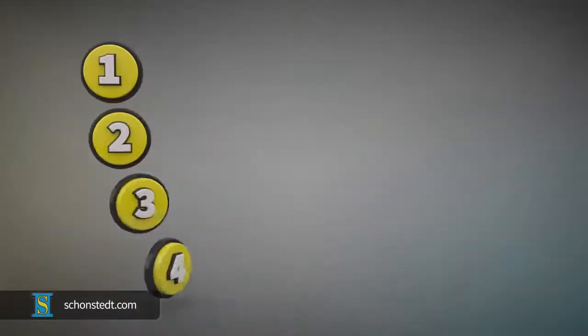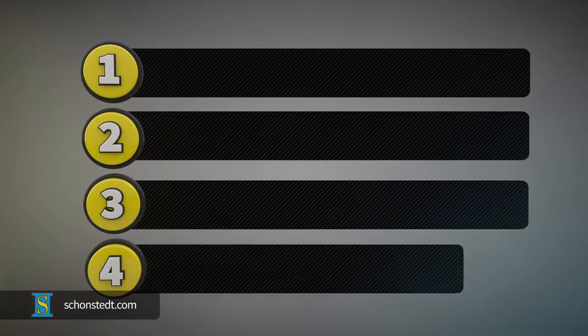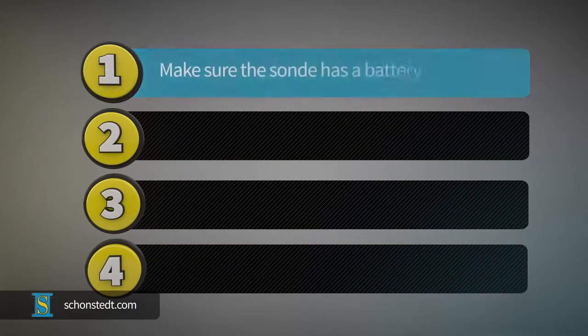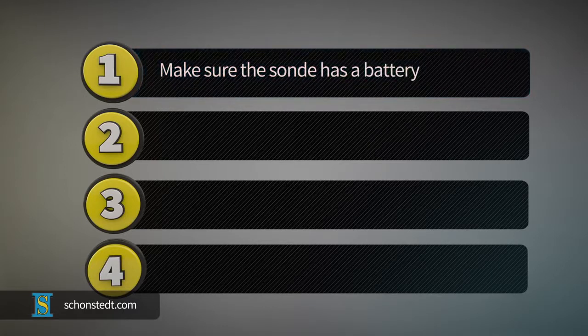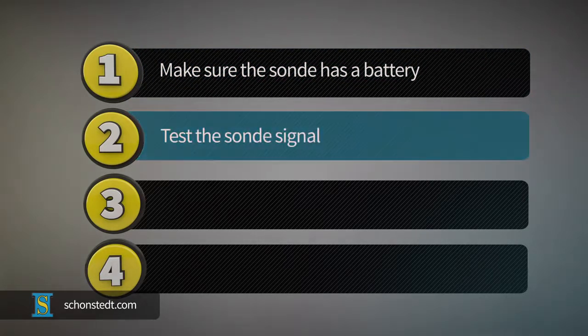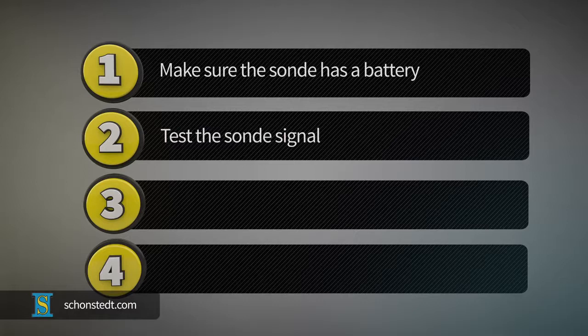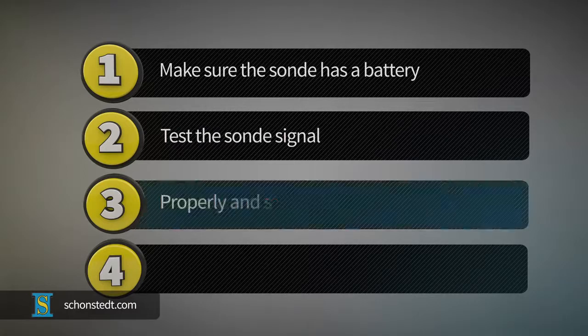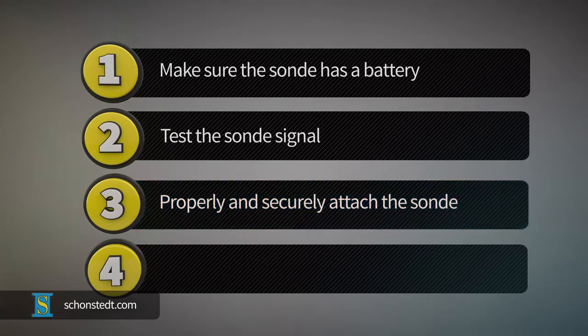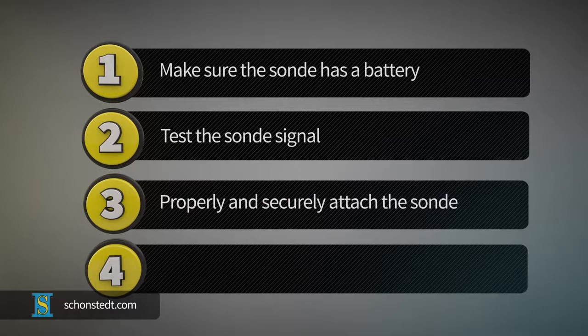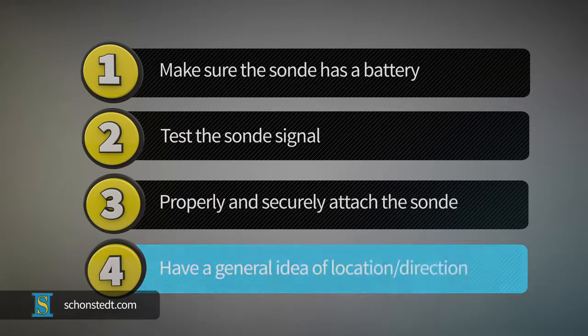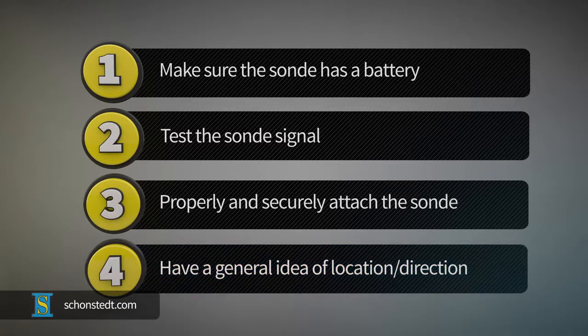In summary, before attempting to locate a sonde, always remember: 1. Make sure the sonde has a battery. 2. Test the sonde signal with your receiver before inserting it into a pipe. 3. Properly and securely attach the sonde to the snake or mechanical means to push it through the pipe. 4. Have a general idea of the location and direction in which the sonde will be moving once inserted in the pipe.